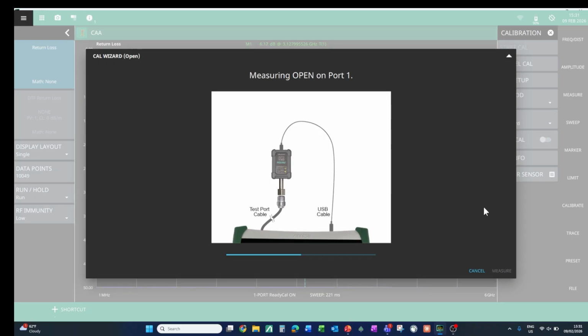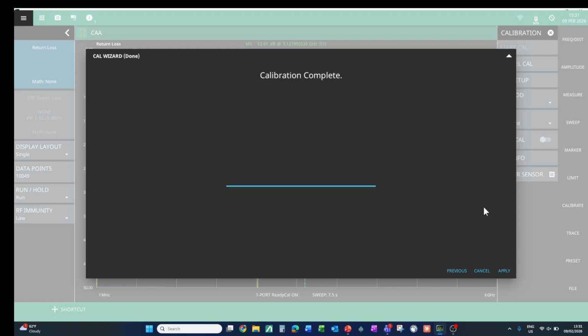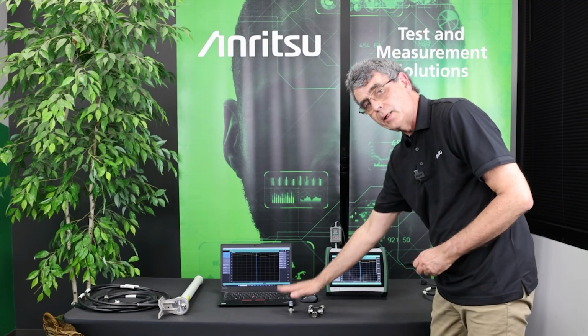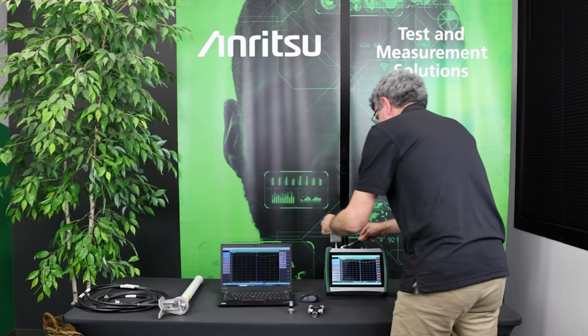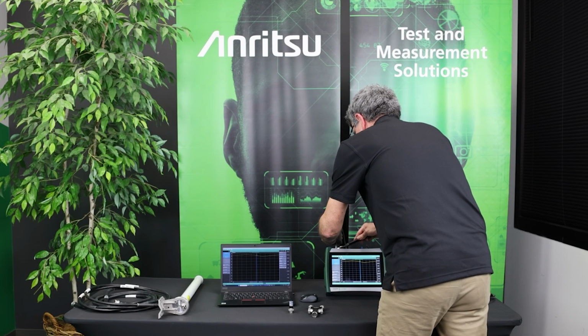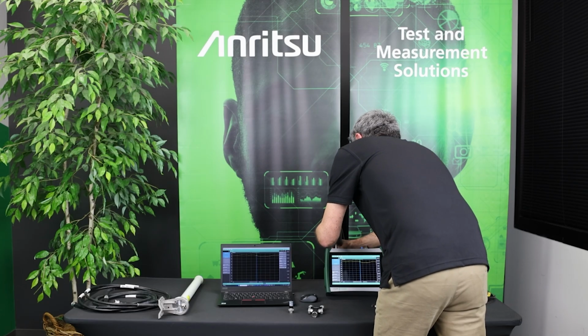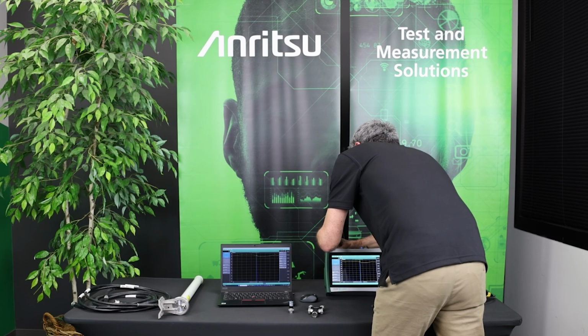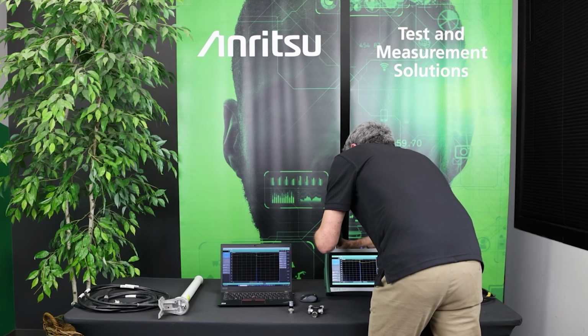it says measuring open, now measuring short, now measuring load, and now the calibration is complete. So I'll apply that calibration data, and now I once again connect the precision load to the test port to compare the return loss that we measure on that precision load. But you can see the benefit of the InstaCal there is that I only had to make one connection to the test port to do the open short load sweep.